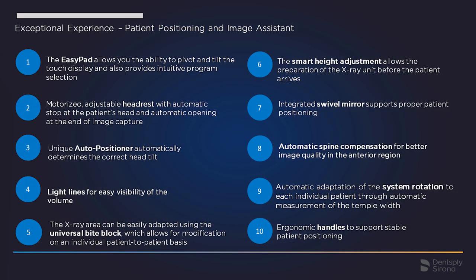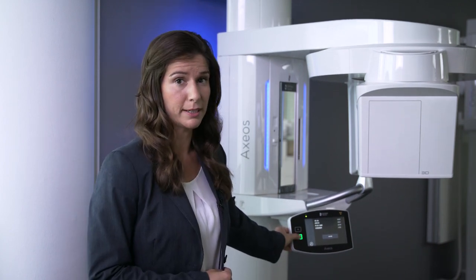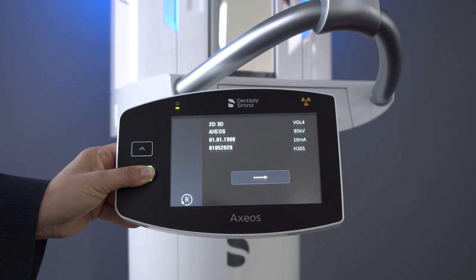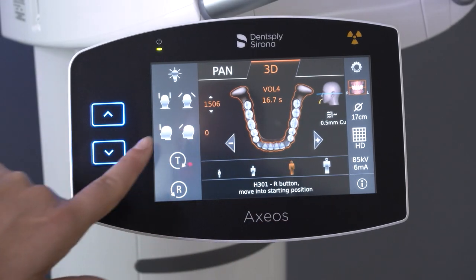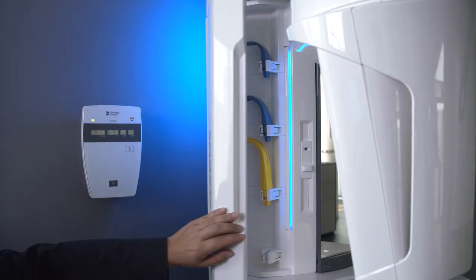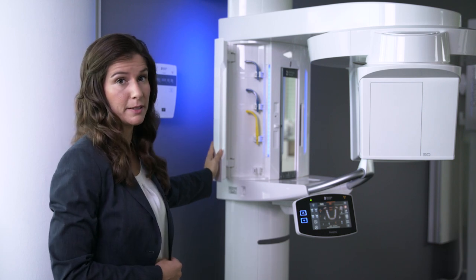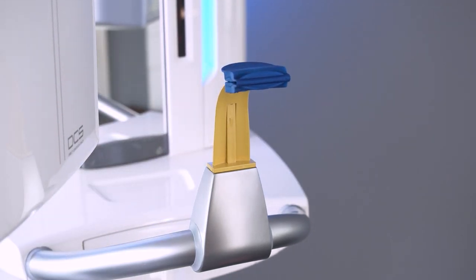Axeos offers a high level of user and patient comfort through the patient positioning and image assistant. It starts even before the patient enters the X-ray room: with smart height adjustment, the assistant can set the unit height to the individual patient's height, so the patient can walk directly into the device with no waiting time. The easy pad guides the user with help messages and color symbols, and bite blocks are always within direct reach thanks to the integrated cabinet. The patented auto-positioner automatically determines the tilt of the head, allowing for reproducible image quality.